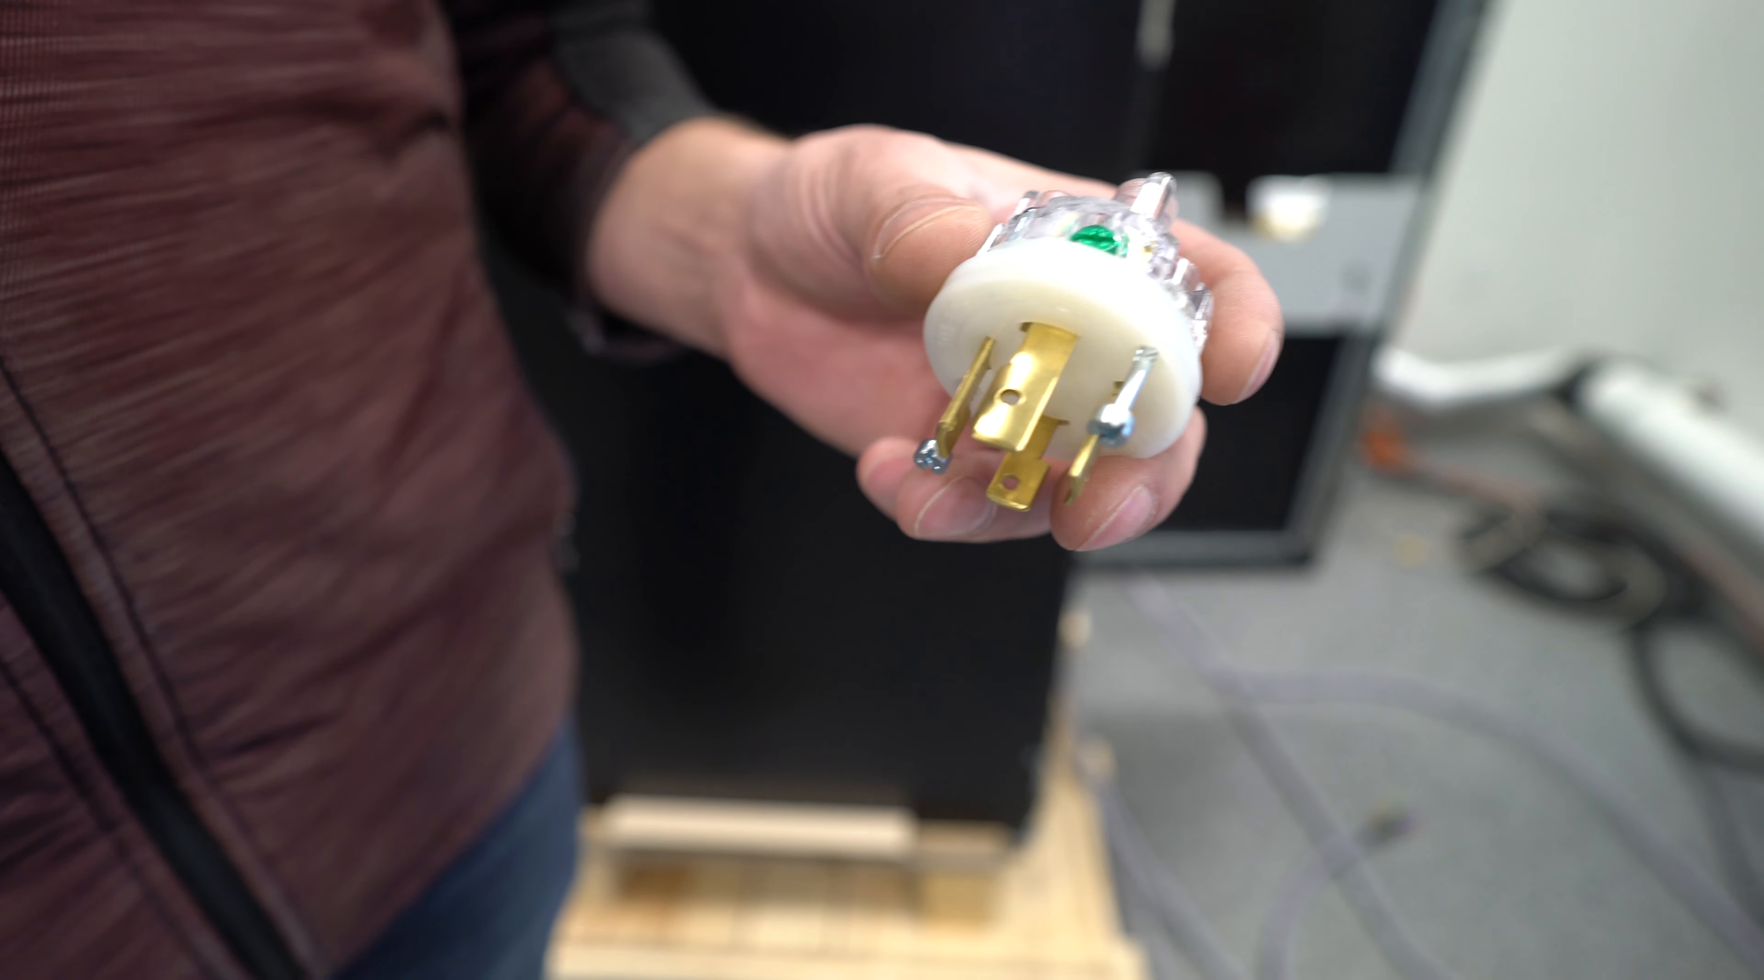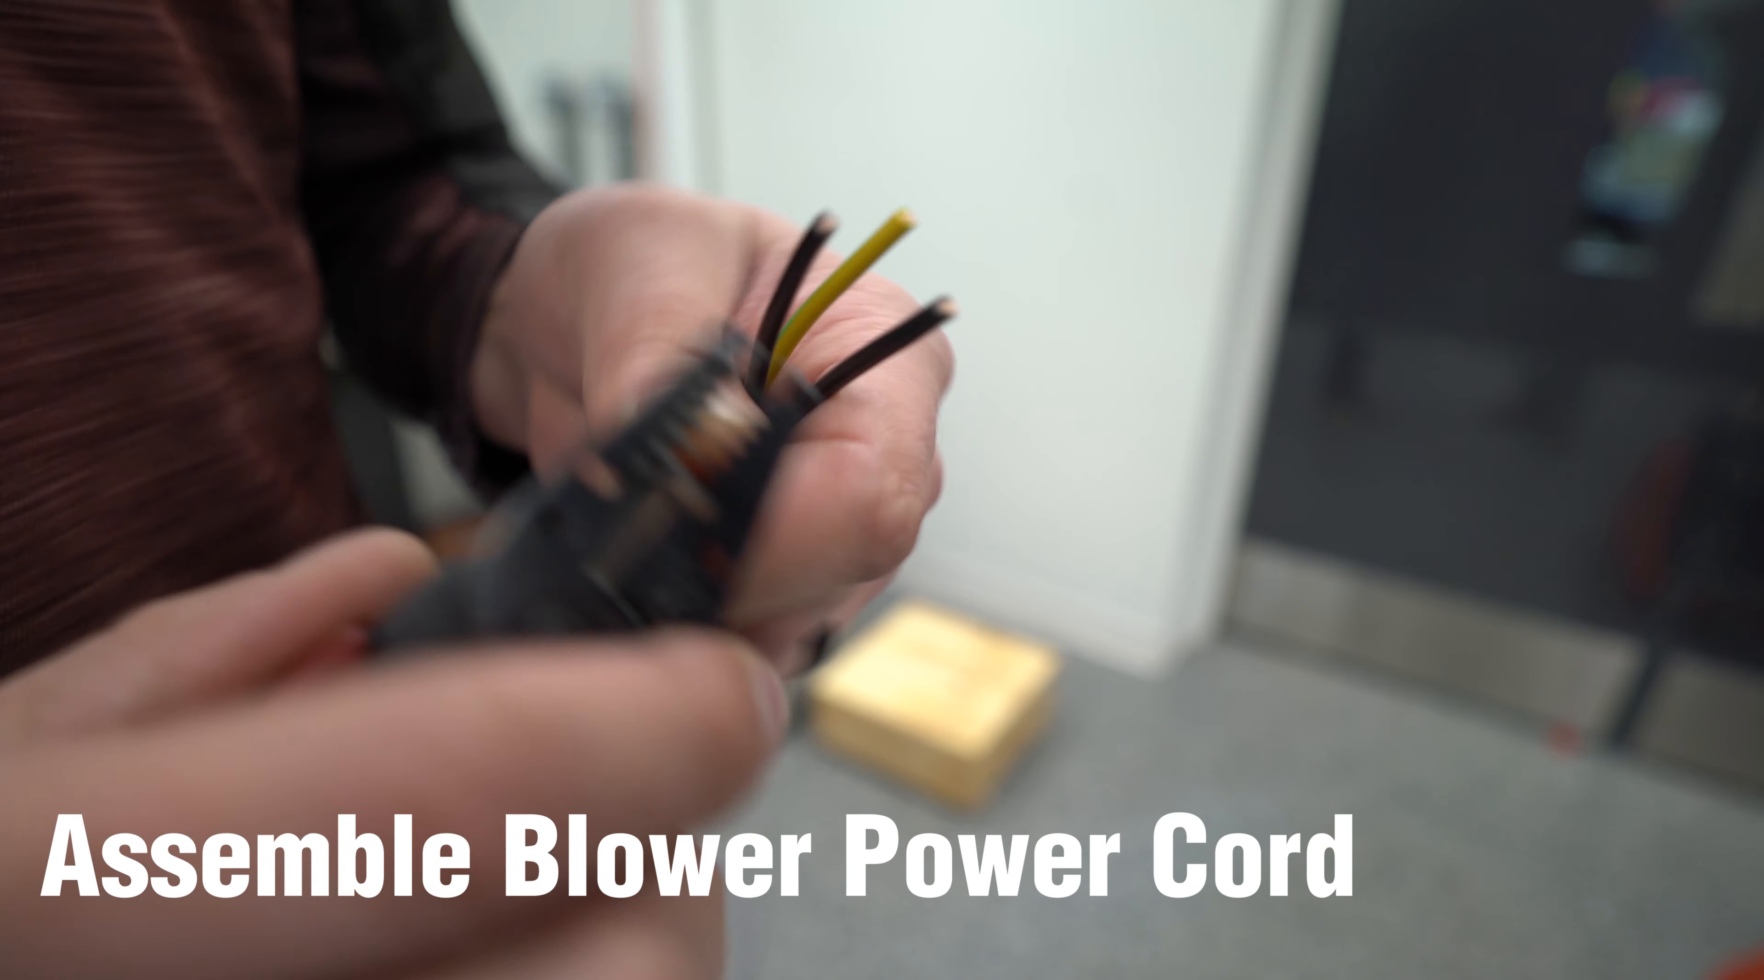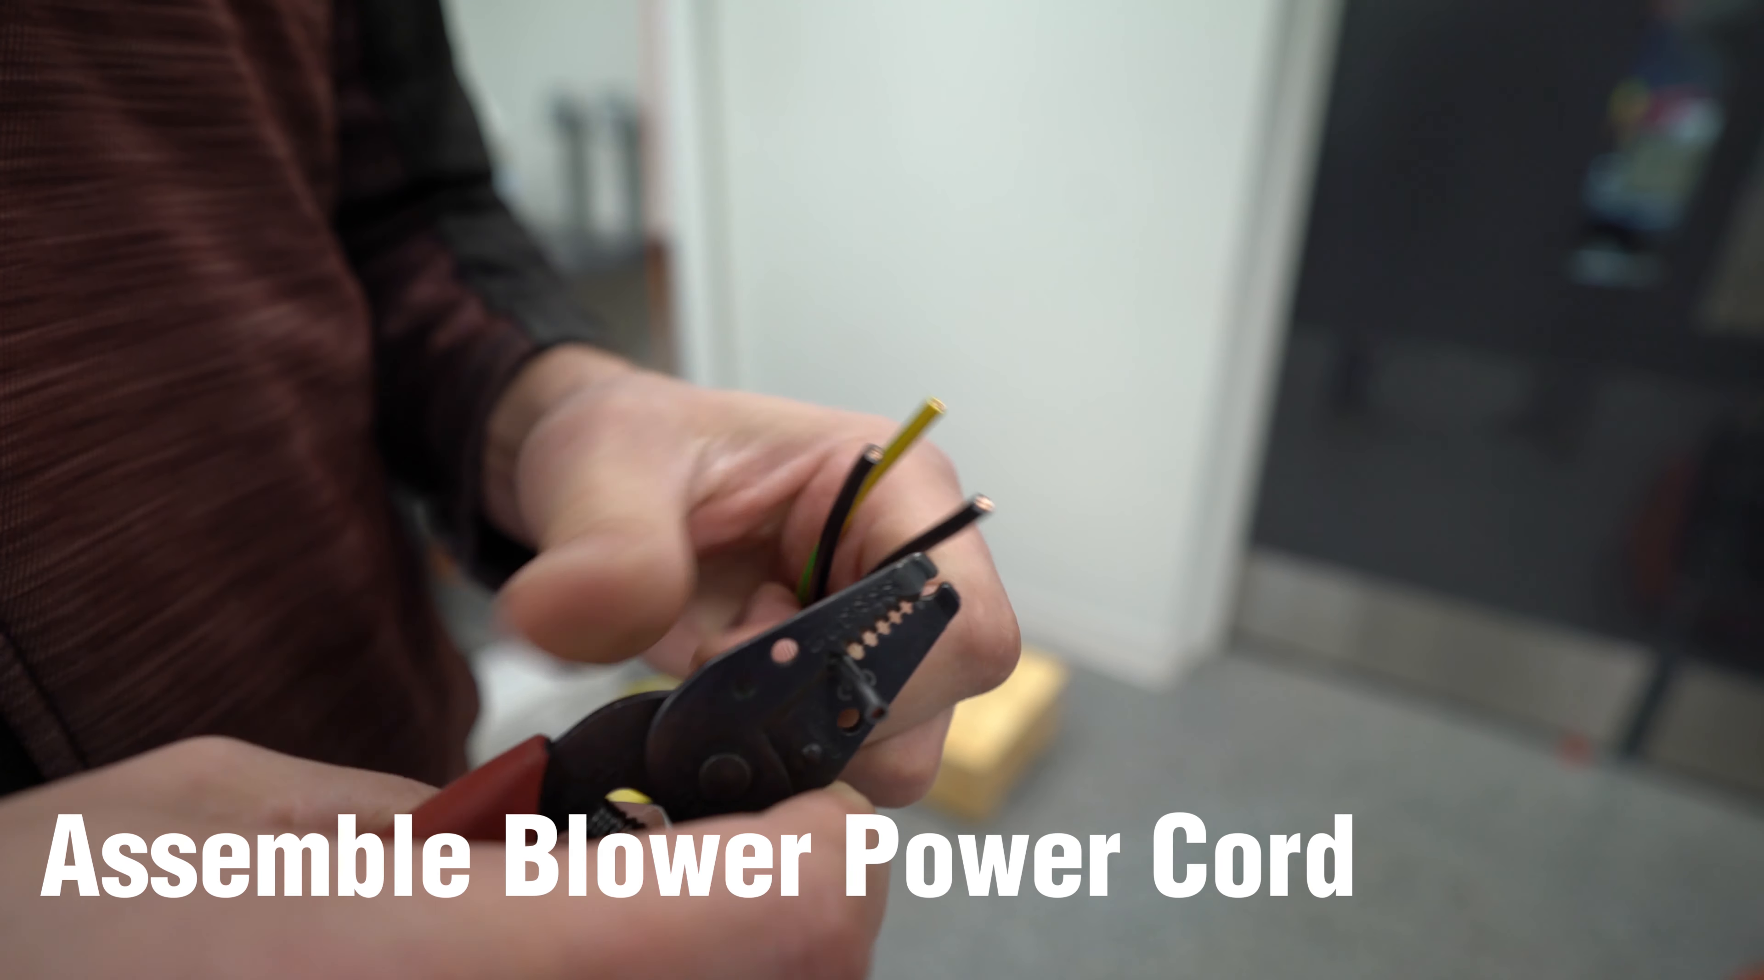Now that we've got all the wires terminated, we're going to go ahead and install the back shell. There should be a keyway on here that you can align to get this to slide on all the way. All set. Go ahead and strip the insulation off of these wires.